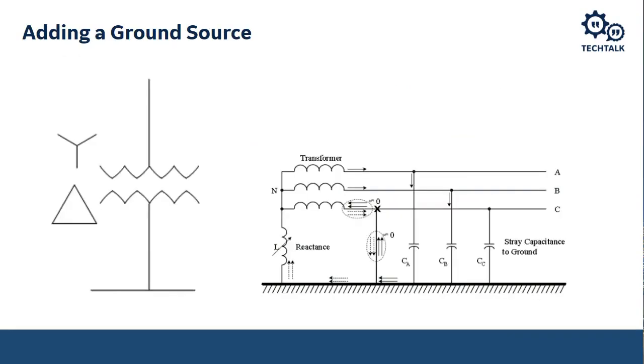So how do we add ground sources? There's a couple of ways to add ground sources, but what does a ground source do? It provides a path to ground. So the impedance to ground, once it's introduced, can limit the ground fault current because it's an impedance to the fault, so we can engineer the fault, and hence we can minimize the associated damage that the fault can cause. We can provide a ground source for other system protections, other zones supplied outside our protection zone, and it makes it easy to detect ground faults because now there is actual, detectable ground fault current flowing, because we've introduced this path to ground.